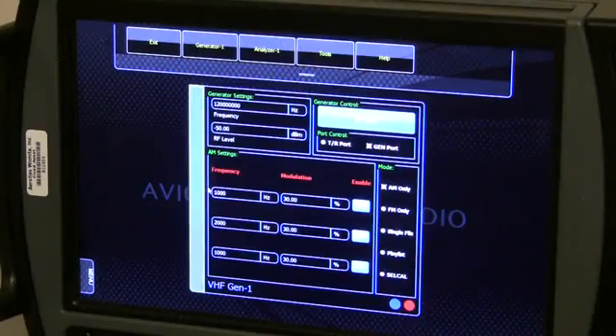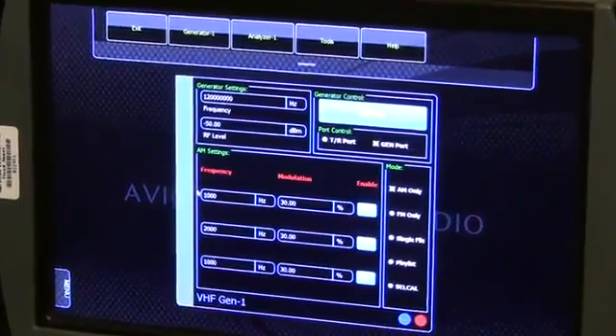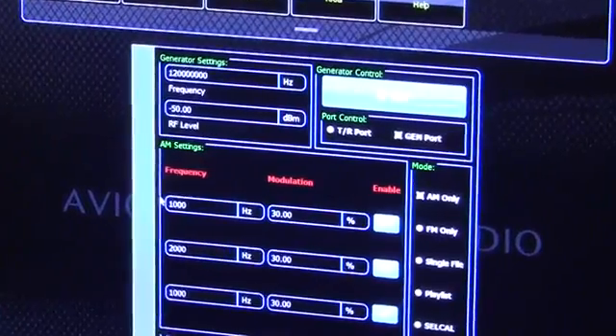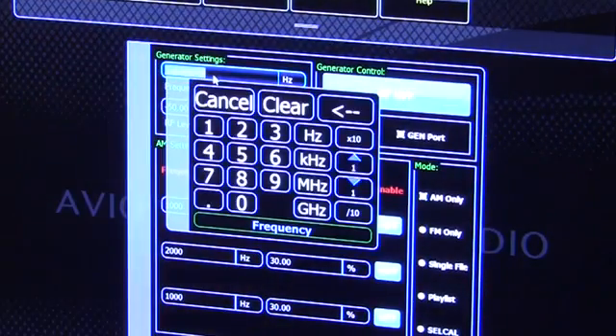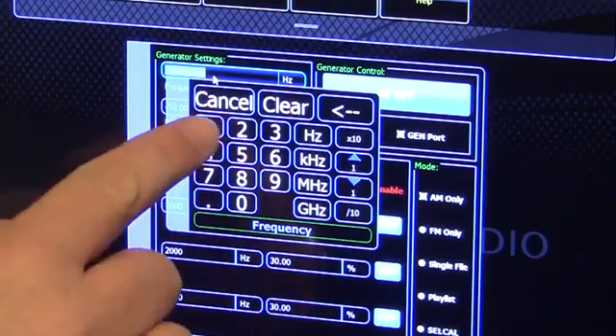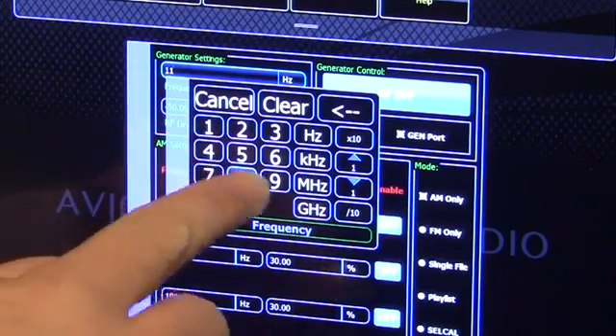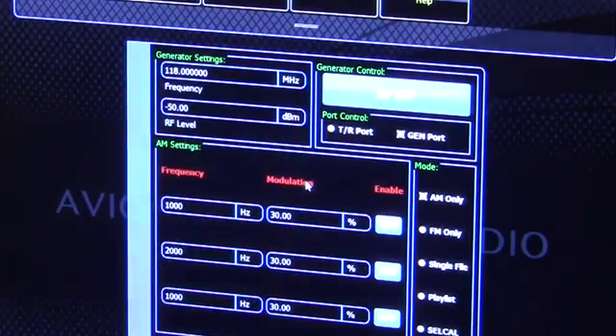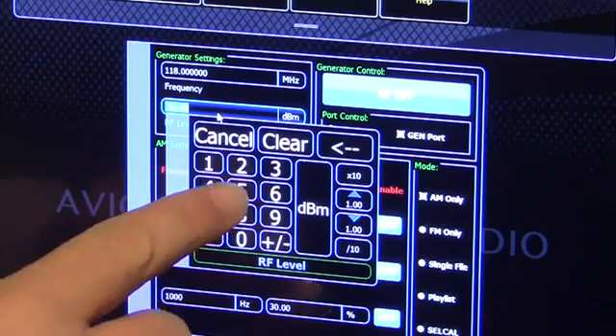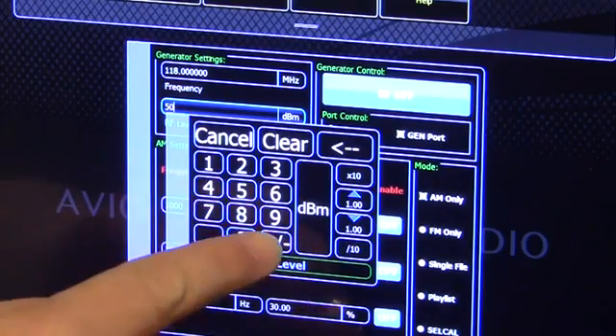The controls are touch-activated and intuitive in design. Let's explore the Generator Settings. By touching the Frequency field, a keypad will pop up and the desired generator frequency may be keyed in. Let's enter a generator frequency of 118 MHz. Likewise, the RF level may be selected — let's select an RF level of minus 50 dBm.